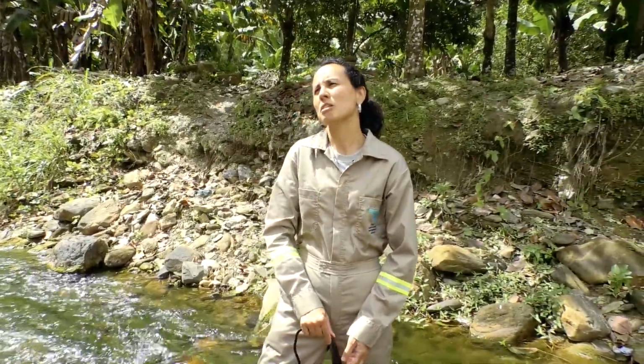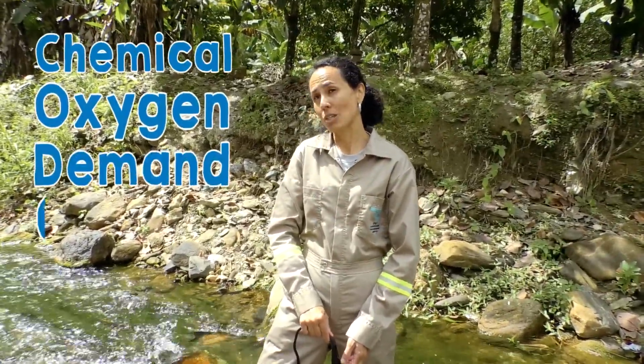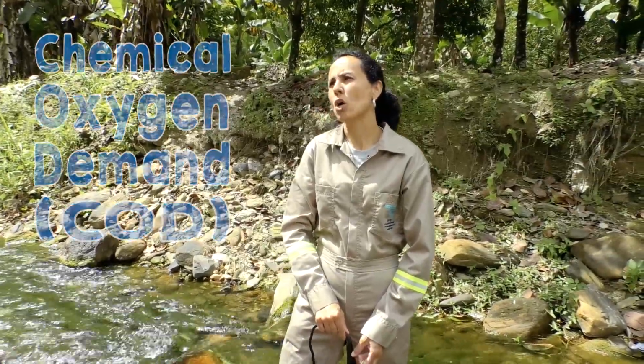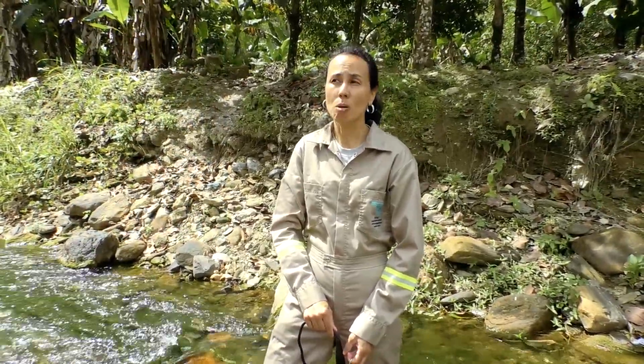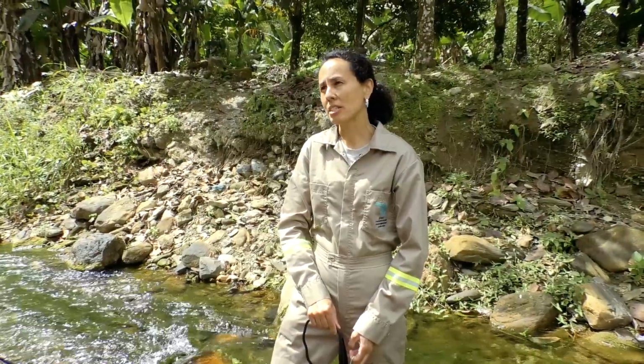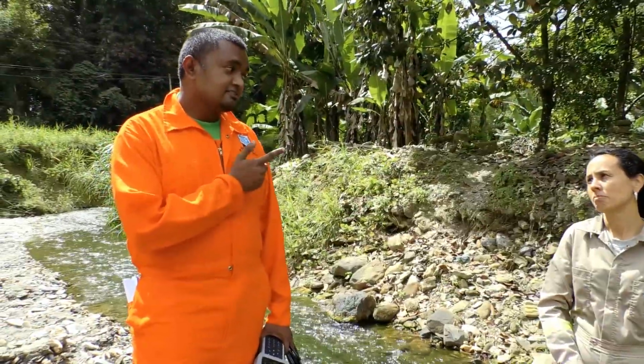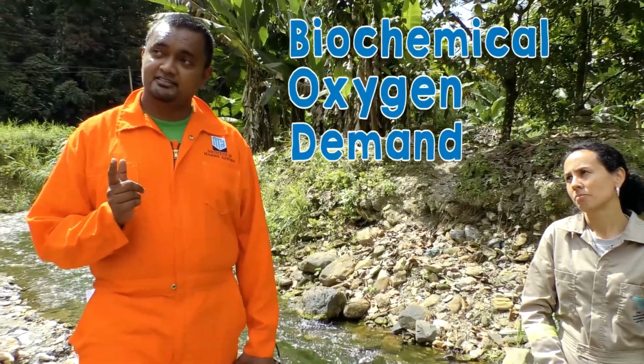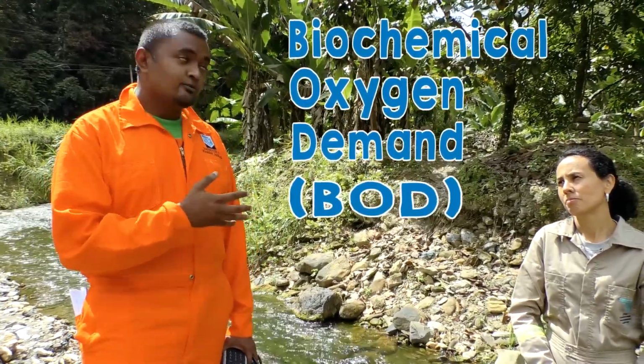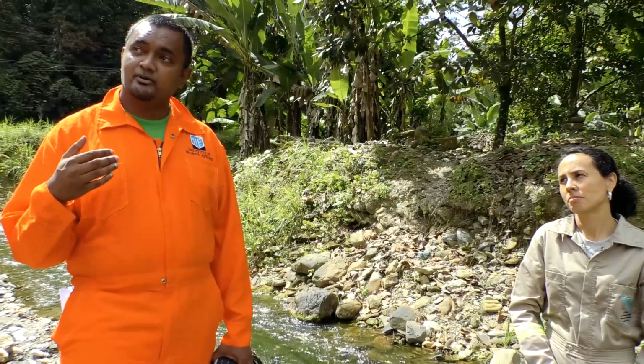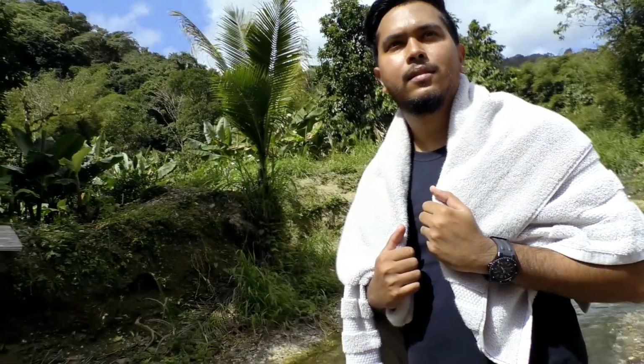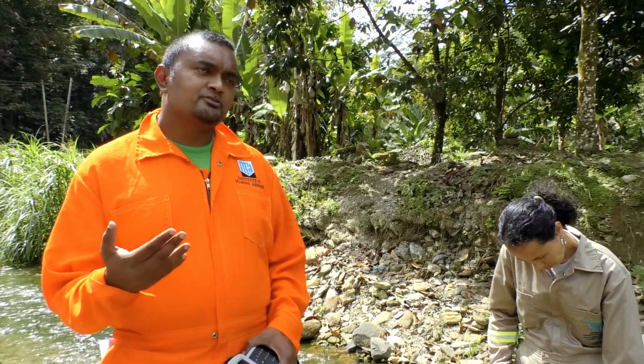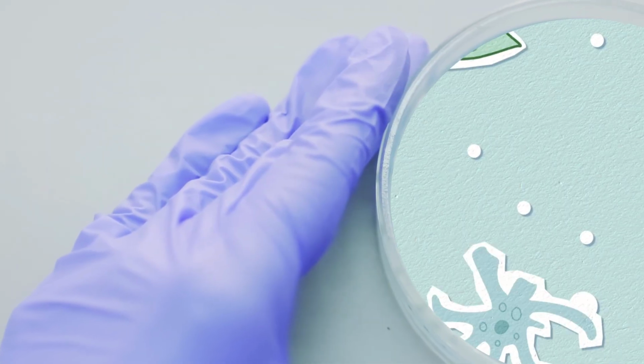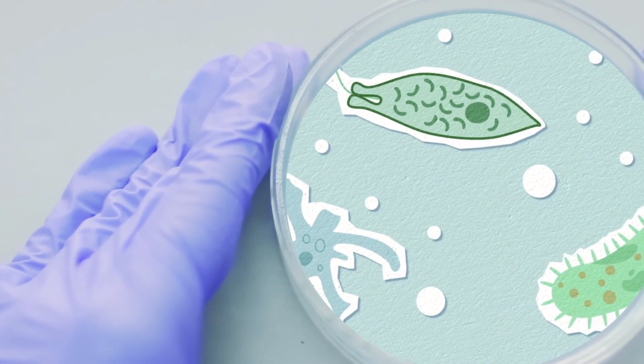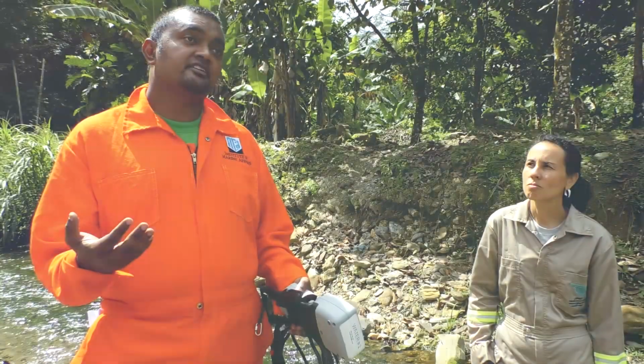But did you know that oxygen is measured by its chemical oxygen demand, COD? Essentially, it is a measure of how much oxygen is required to oxidize organic compounds in the wastewater into carbon dioxide and water. Correct. Plus, there's also a 5-day biochemical oxygen demand test, where a sample is taken to the lab, where we measure the amount of dissolved oxygen that is required by aerobic organisms. Basically, we're measuring the amount of oxygen that is used by aquatic microorganisms to break down organic matter at a specific temperature, say 20 degrees Celsius, over a period of 5 days.